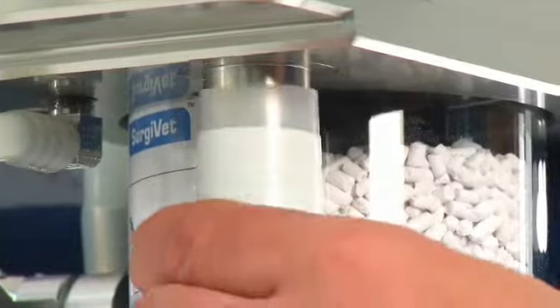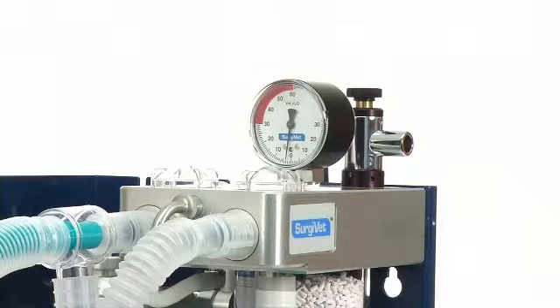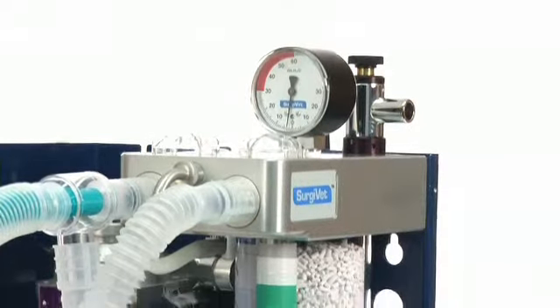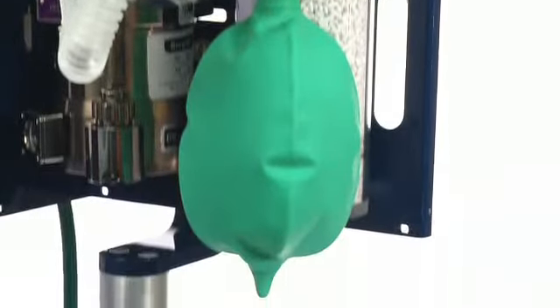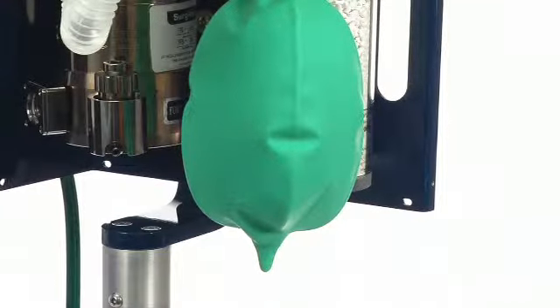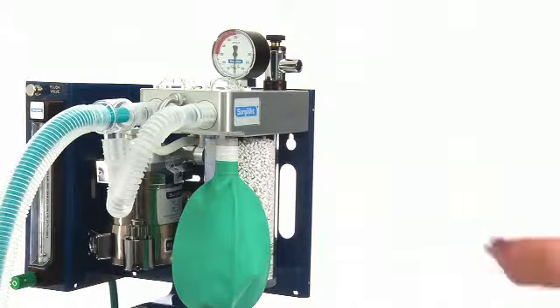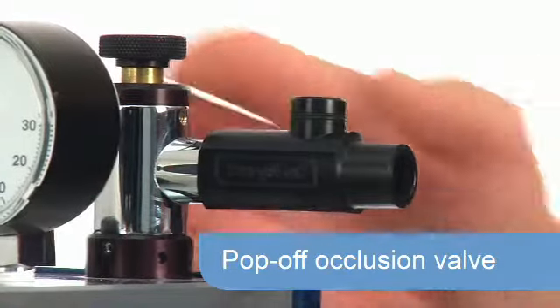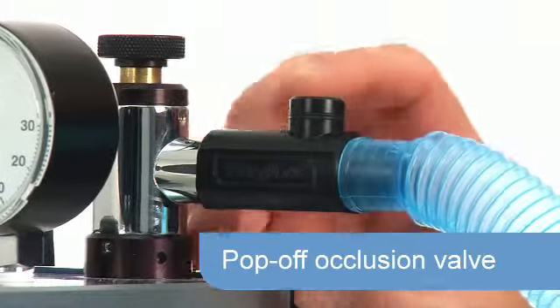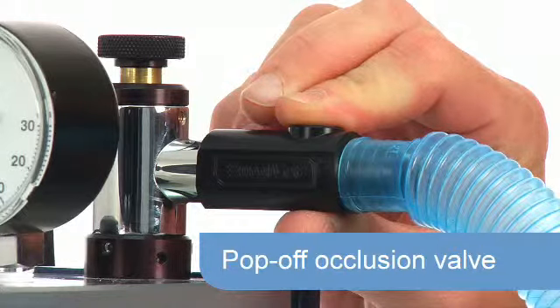This adjustable valve directs waste anesthetic gas from the machine to the scavenging system. The unique feature of the Surgivet pop-off valve is that it will passively hold 2 centimeters H2O pressure in the system when in the fully open position. This maintains a passive volume in the breathing bag. The pop-off occlusion valve connects to the outlet of the pop-off valve. By depressing the occlusion valve button, gas is blocked from exiting the pop-off valve so that a manual breath can be given to a patient.